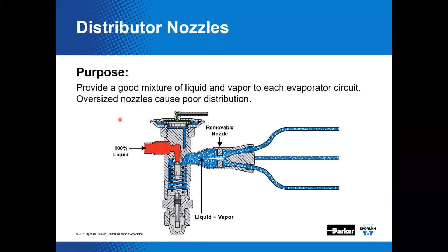We've got an appropriately sized nozzle that helps create a high pressure drop and velocity imposed on that two-phase flow. That causes those two phases to mix together — it helps keep the phases mixed and facilitates good distribution. That mixture is then introduced into each evaporator circuit via the circuit tubes. The nozzle and circuits are all critically sized distributor features for a given application.